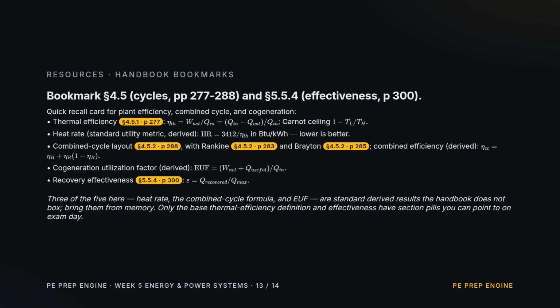Bookmark the cycle pages. Thermal efficiency, net work over fuel in, with the Carnot ceiling. Heat rate, 3412 over efficiency, in BTU per kilowatt hour. Lower is better. The combined cycle layout, with the Rankine and Brayton cycles, and the combining formula, eta Brayton plus eta Rankine times 1 minus eta Brayton. The cogeneration utilization factor, power plus useful heat over fuel in, and recovery effectiveness, recovered over maximum. Remember, three of these, heat rate, the combined formula, and the utilization factor, are standard results the handbook does not box. Bring them from memory. Only thermal efficiency and effectiveness have pages to point to.